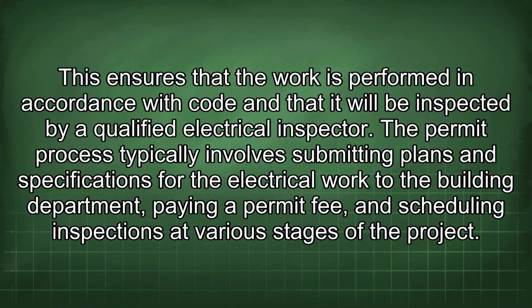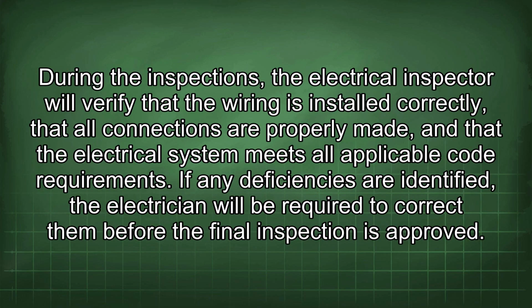The permit process typically involves submitting plans and specifications for the electrical work to the building department, paying a permit fee, and scheduling inspections at various stages of the project. During the inspections, the electrical inspector will verify that the wiring is installed correctly, that all connections are properly made, and that the electrical system meets all applicable code requirements. If any deficiencies are identified, the electrician will be required to correct them before the final inspection is approved.